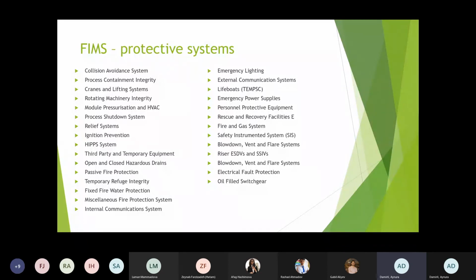Emergency power supplies, to provide reliable and secure power supplies to all essential equipment during an emergency situation. This will establish essential command, control, and communication facilities for platform management in order to enable an effective and safe emergency response. The emergency power is to be in a functional condition, available to provide power to essential users on loss of main platform power at all times, unless alternative arrangements are in place as agreed with our high-level management.